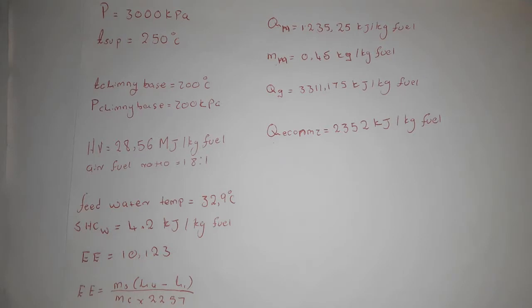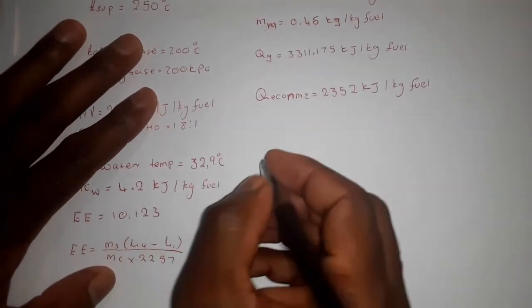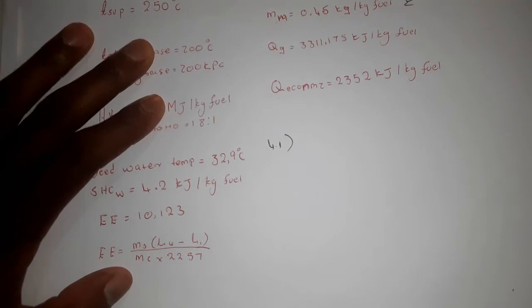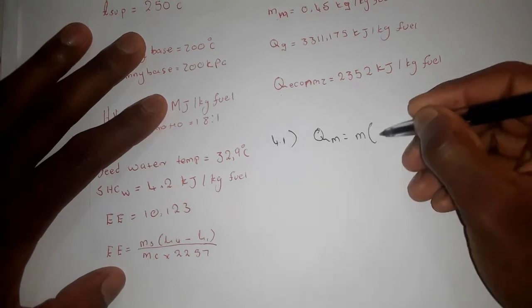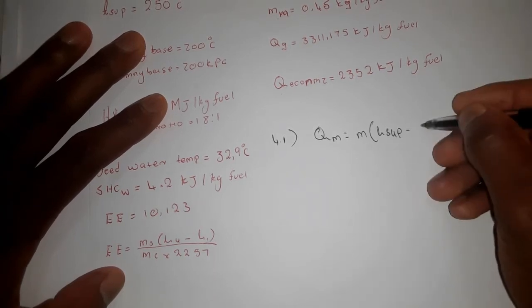For question 4.1, we calculate the atmospheric temperature. We use the formula for heat energy that went out with the moisture, since we have the mass of moisture and that formula contains the atmospheric temperature. The heat energy that went out with the moisture equals mass times (H_superheat minus H_atmosphere), where H_atmosphere uses the specific heat capacity times the atmospheric temperature.